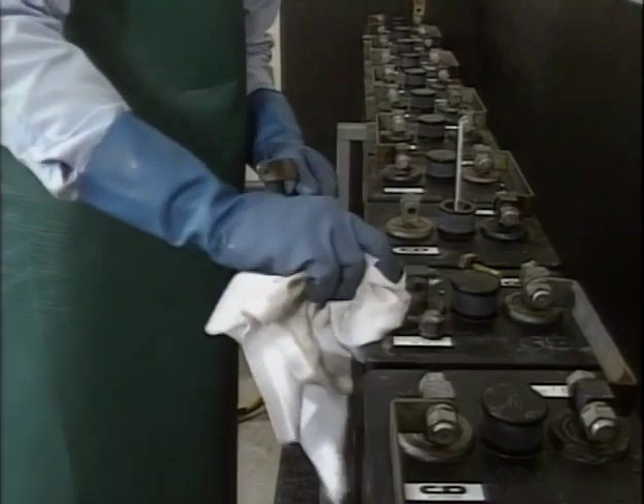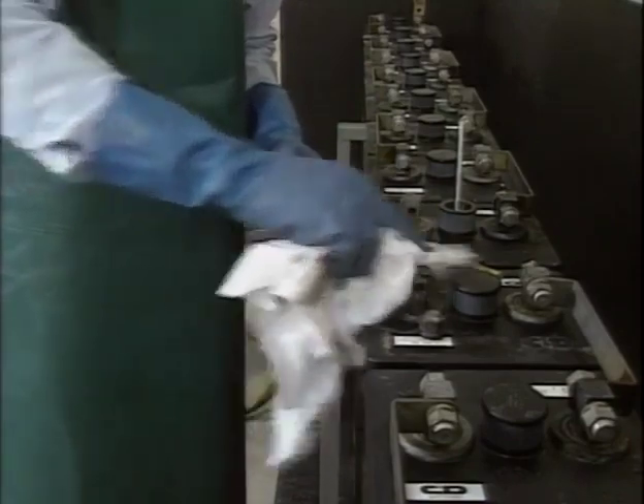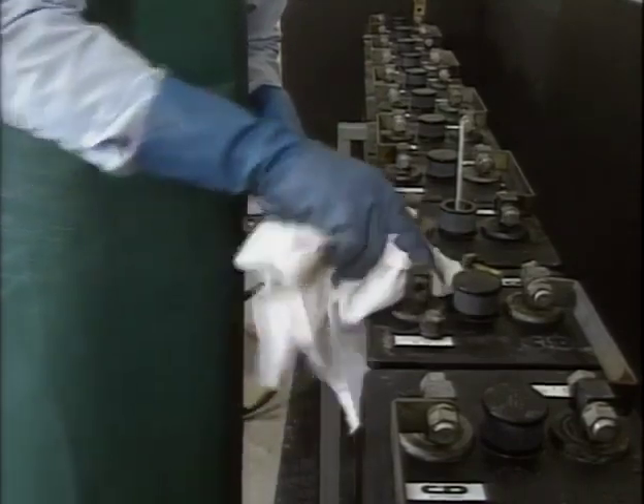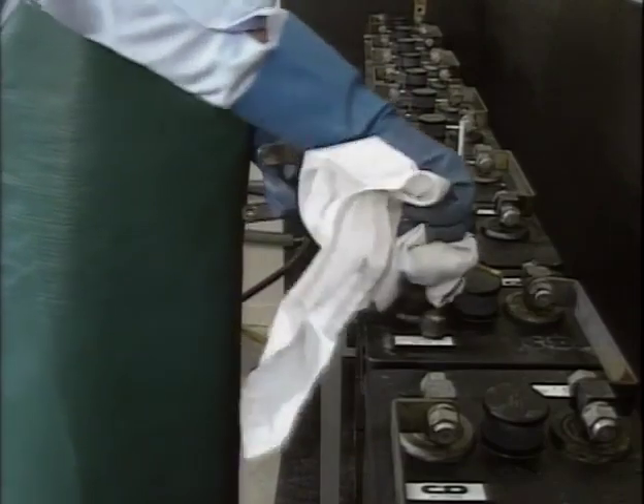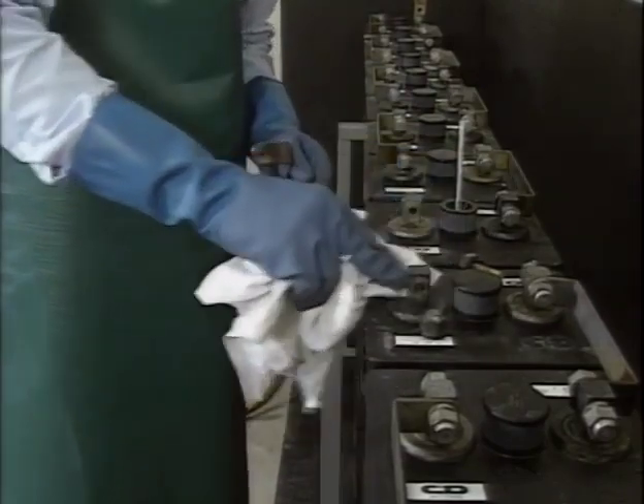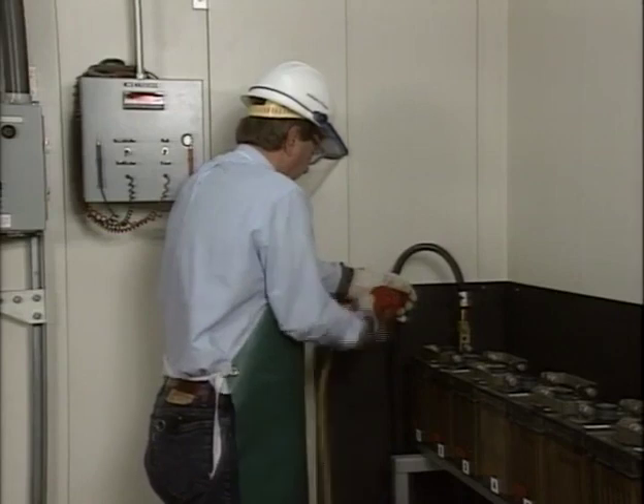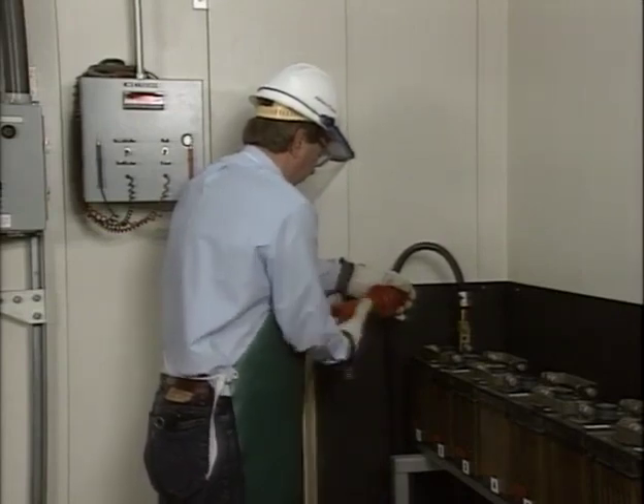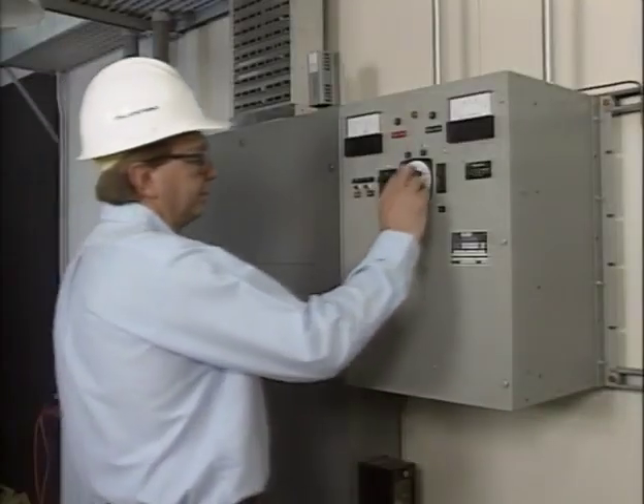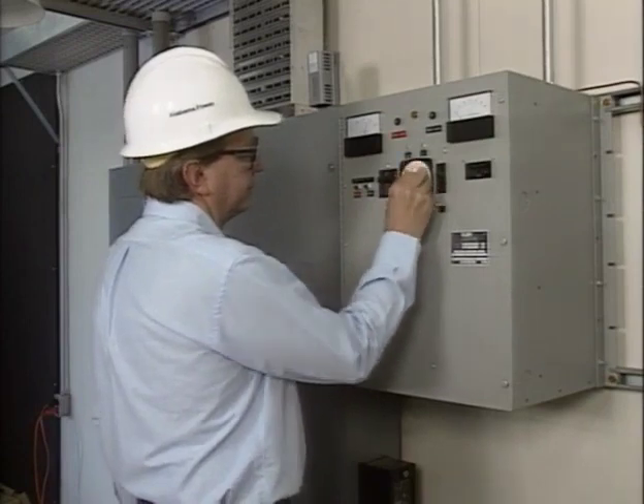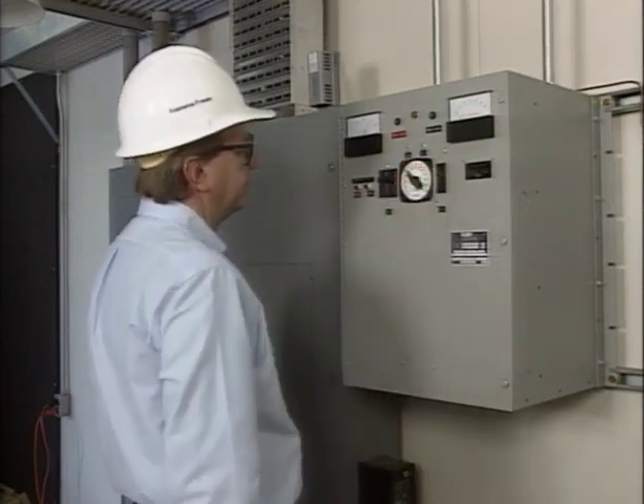If the battery passes the capacity test, any high resistance connections that were noted are cleaned and rechecked for resistance using a digital micro-ohm meter. Then the battery is returned to service according to company procedures. Typically, the battery is given an equalizing charge to restore it to full charge.